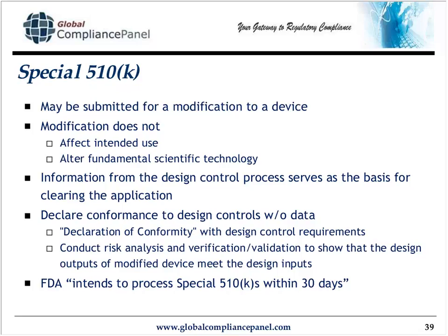That's the information you're providing. It's okay to declare conformance to design controls without providing the data. You're going to provide a declaration of conformity. You're certainly going to have conducted a risk analysis to show that the design outputs meet the design inputs.